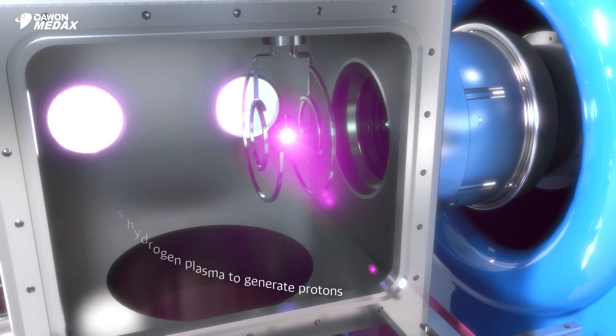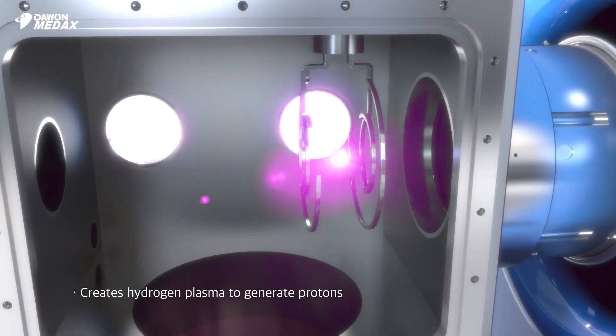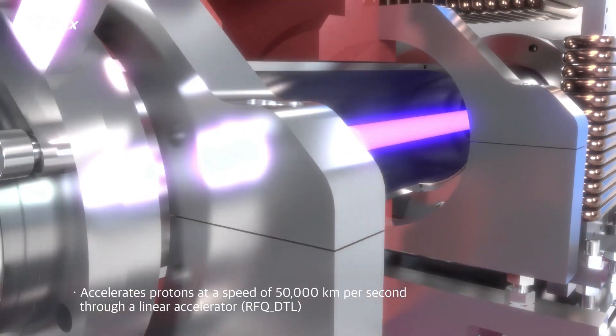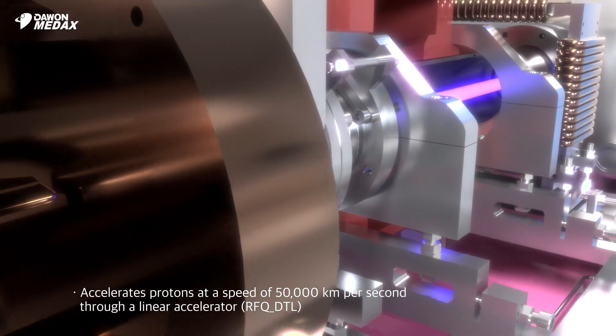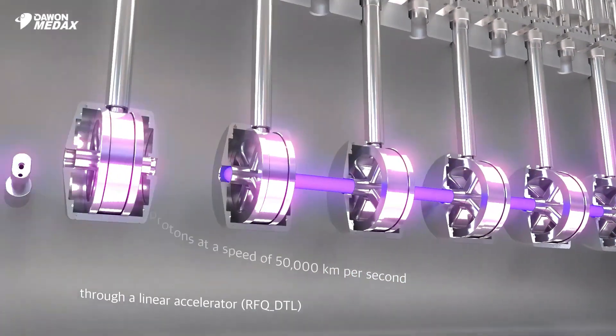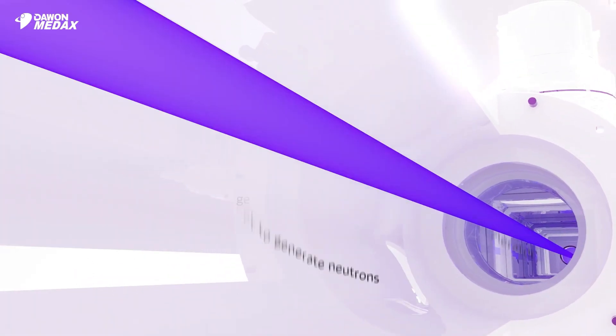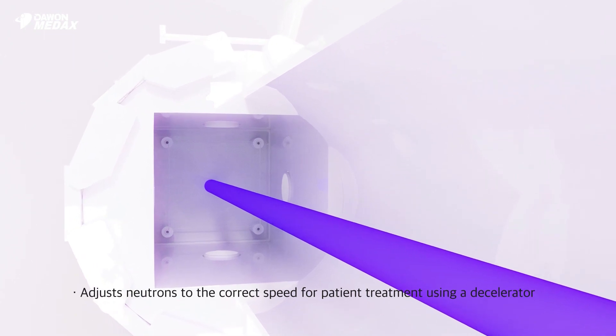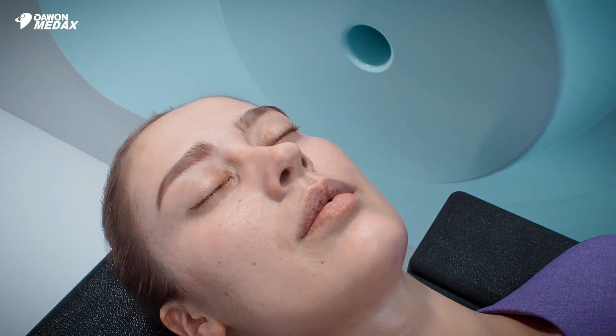BNCT, developed by Dawon Medax, accelerates protons generated by hydrogen plasma inside the injector up to a speed of 50,000 kilometers per second through a linear accelerator. The accelerated protons collide with the beryllium target to generate neutrons, which are decelerated to appropriate energy for the treatment.